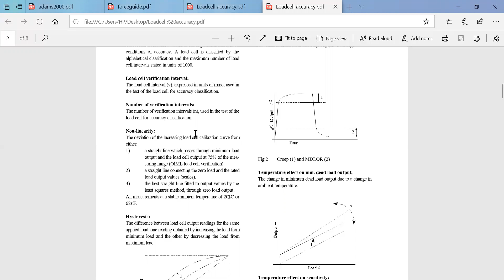The third is the best straight line fitted to the output values by the least square method through the zero load output. Sometimes we also fit the curve to the variation you get between the measured and the actual by the linear regression method. When we use linear regression methods, we usually fit the curve with respect to the theoretical nature of the curve. So when you try to fit the obtained graph with the theoretical curve, if it is not mapping with the zero load output graph, then you can tell that it is not a linear version. It is a non-linear type of variation that you are getting when the load is increased in the given load cell. So all these criteria show how it is varying non-linearly. These are the three parameters within which it has to fit if you have to classify the reading under non-linearity.